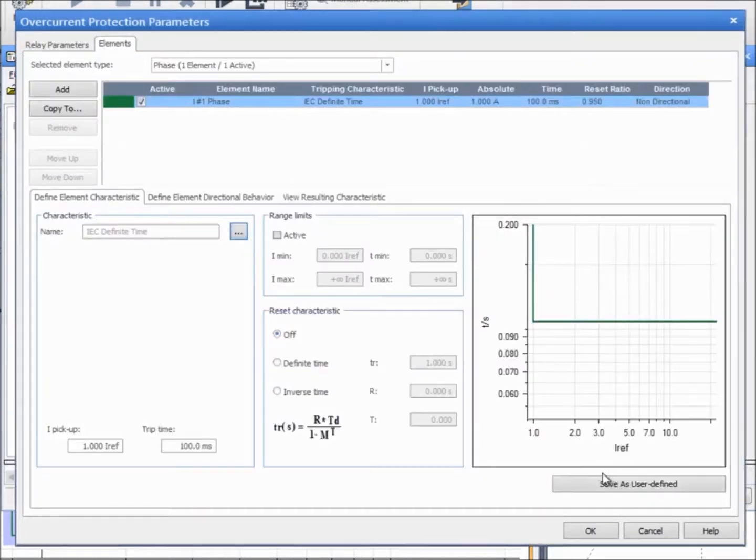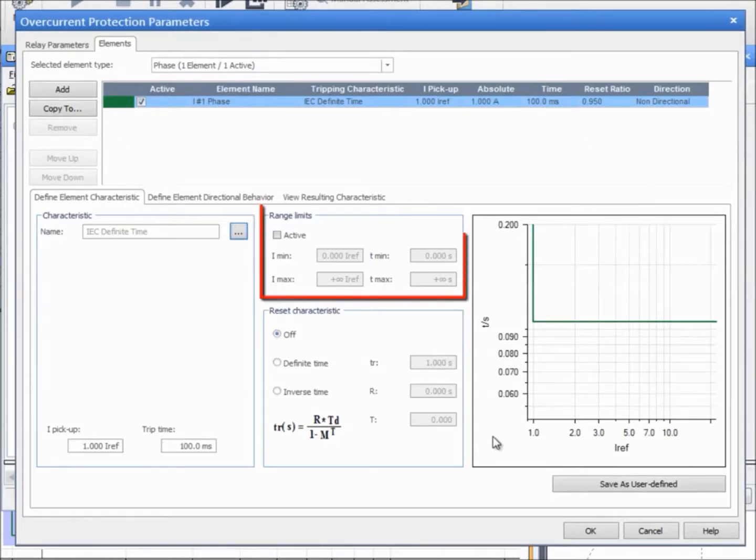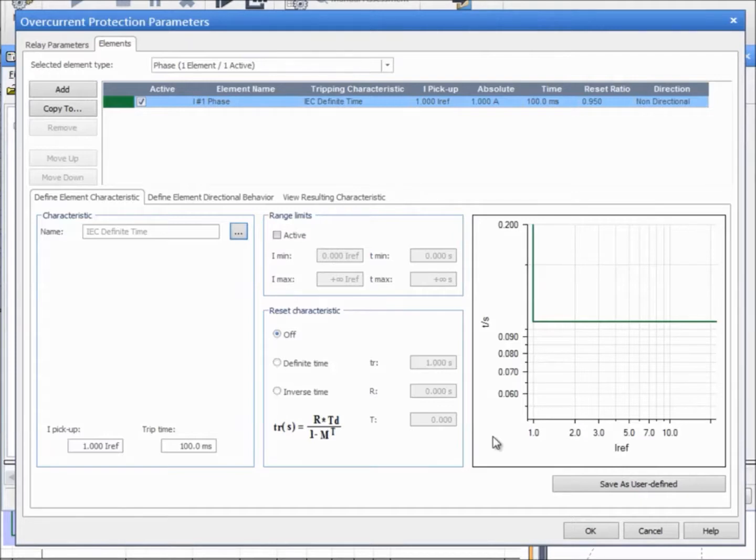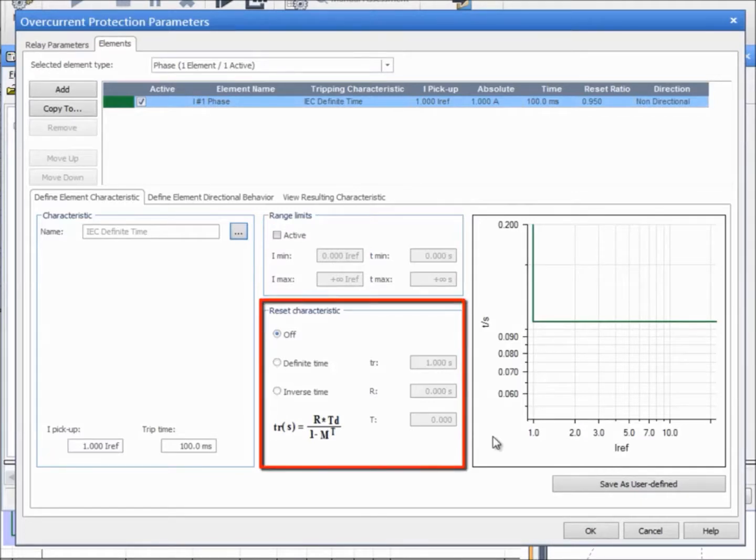The characteristic to be tested can be restricted in the Range Limits section. Testing characteristics with a minimum tripping time is a typical application example for this feature. It is also possible to define definite or inverse time reset curves to test a relay with a reset characteristic.